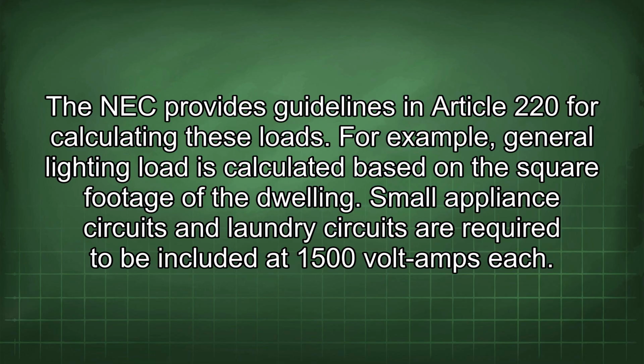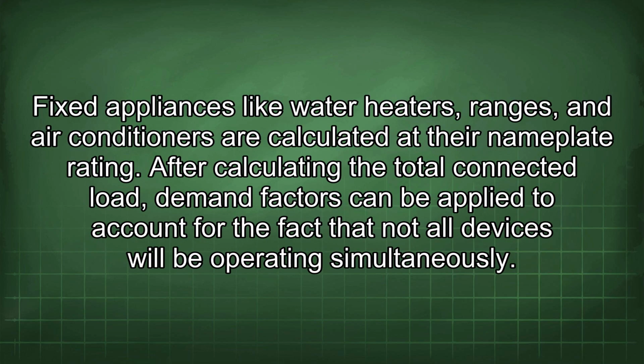For example, general lighting load is calculated based on the square footage of the dwelling. Small appliance circuits and laundry circuits are required to be included at 1500 volt-amps each. Fixed appliances like water heaters, ranges, and air conditioners are calculated at their nameplate rating.